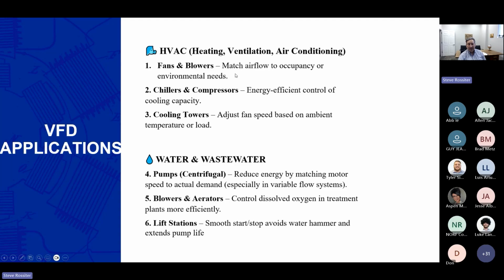But for example, in a fan or blower, you have facilities all over the country that have old technology that might be using bypass valves on a pump or a throttling valve or a throttling damper. And if you approach matching the airflow to the occupancy needs or the environmental needs by just reducing the speed of the motor, you get that large savings, which in most of those kind of applications easily is in the 20 to 30% range. And of course, when there's light occupied conditions, but still need to have airflow, even much greater than that, to the point where it's probably common practice now for almost every design engineer, mechanical and electrical, to implement variable frequency drives in new buildings that would have fans or pumps.